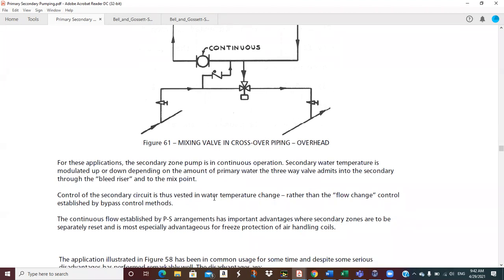But you got to buy these three-way valves and this, that, and the other. And, you know, it's cheaper to turn a pump on and off, because you got to have that little pump anyway. So you just turn it on and off under the action of the thermostat. You don't get as good control, but the guy paying for all the equipment doesn't have to spend as much money. So there you go.